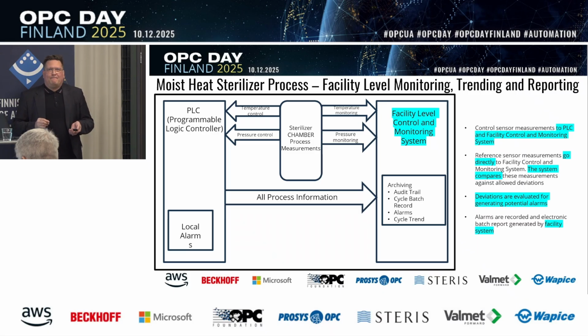I'm not saying this applies to 100% of situations, since many sterilizers are manually operated for loading and unloading. That gives you the dilemma of equipment safety when you still have people in the area, especially with smaller sterilizers. Not very often do you see an automated platform running loads in and out of the system. Building that sort of automation around smaller sterilizers isn't easily justified.